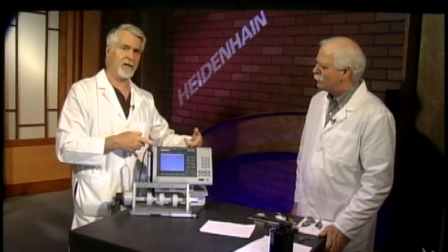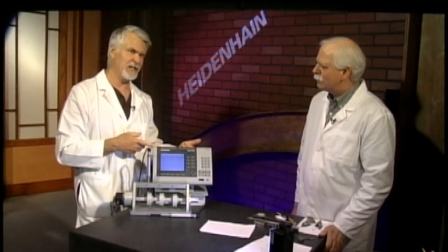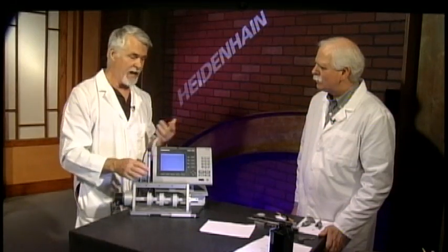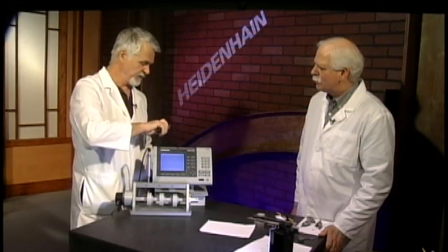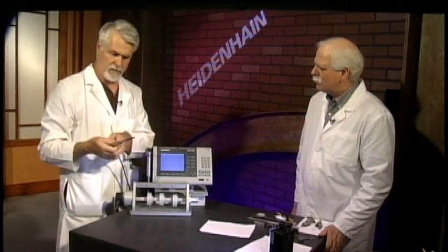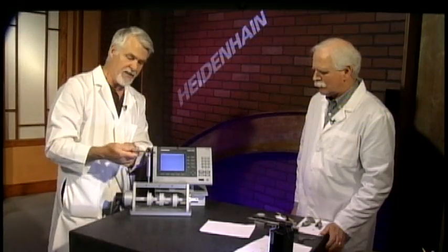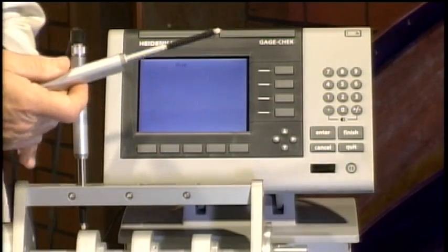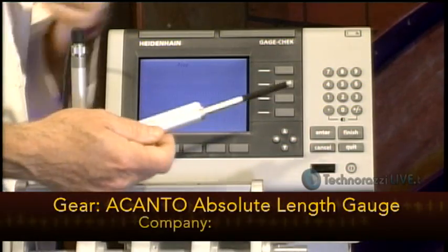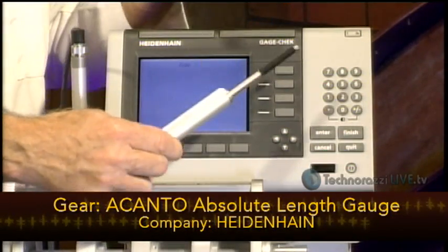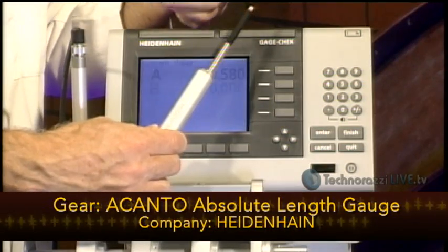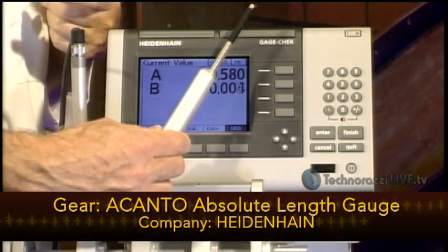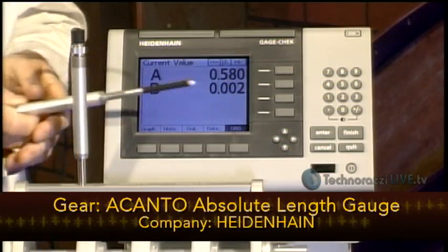So the Gage Check product is really what addresses this. This particular model, the ND2100G, accepts up to 8 gauge inputs. We happen to have 2 gauges with us today. These are linear measurement gauges from Heidenhain. I'll run you through real quick what this does. This happens to be an Acanto gauge. This has a 2 micron accuracy over the full travel of the gauge, which I believe on this one is 25 millimeters. And let's take a look at the Gage Check here.